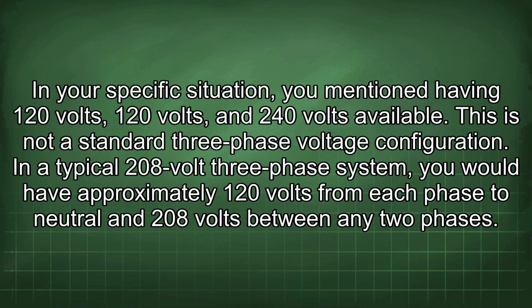In your specific situation, you mentioned having 120 volts, 120 volts, and 240 volts available. This is not a standard three-phase voltage configuration. In a typical 208-volt three-phase system, you would have approximately 120 volts from each phase to neutral and 208 volts between any two phases.